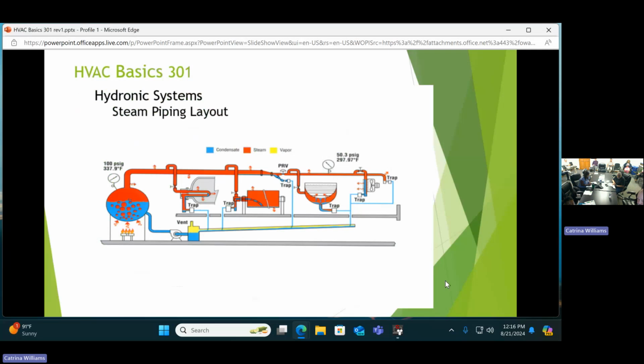The yellow you see here, that condensate's still very, very hot. So start out with 250 degree, 15-pound steam. It drops in temperature a little bit, but it's still pretty hot and above 212. So as it gets in these pipes headed to this condensate receiver, it can flash back into steam. So there's a vent up here, and you've seen manholes in New York City where there's steam coming up through there. They're venting off that excess steam off of that piece of equipment. And a lot of times in industrial plants, you'll see a plume of steam coming off of a building. They run that vent up to a roof to get it so it's safe to vent that steam. But that's just a basic configuration of different pieces of equipment, how a steam and condensate circuit works.